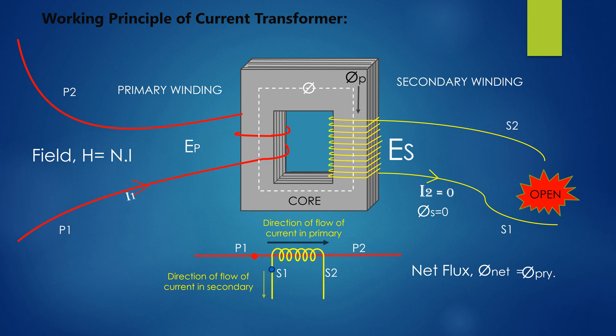As CT burden is low, a few VA, 15 VA to 30 VA, and therefore operating voltage of the secondary winding is generally low. The insulation of secondary winding is used according to such voltage. Beyond this voltage may cause insulation failure and fire hazard. This may cause danger to personnel working on secondary side. Therefore, when primary current is flowing, secondary should never be disconnected.